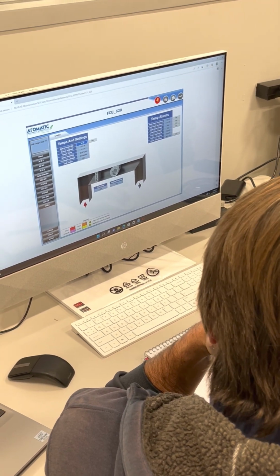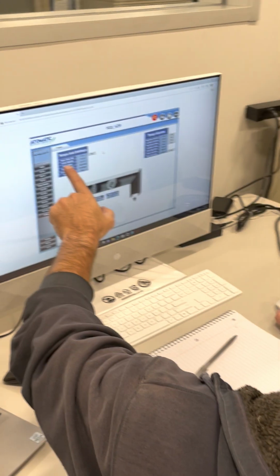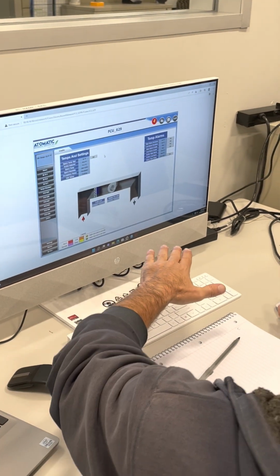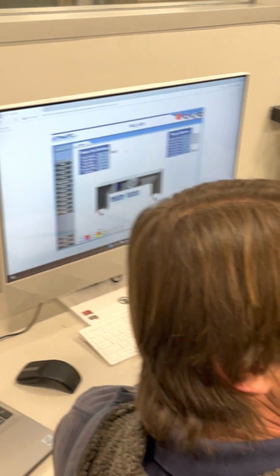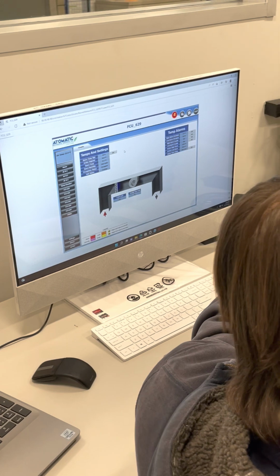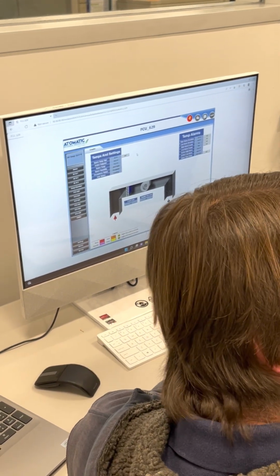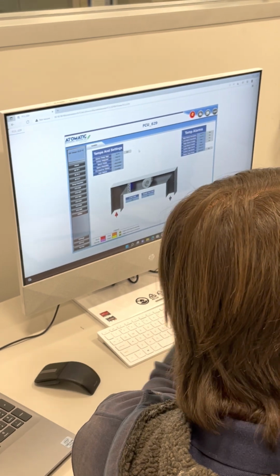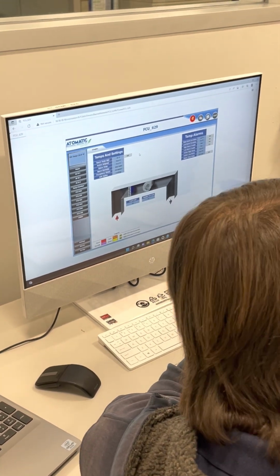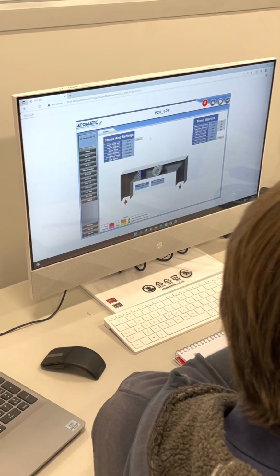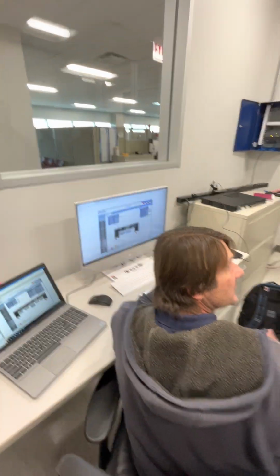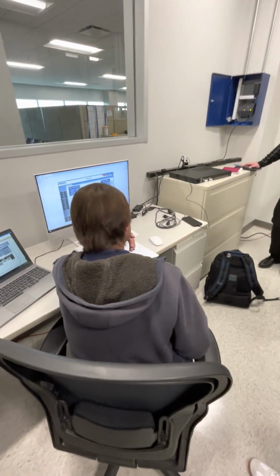You'll see that 70, and then in a minute, that active set point will drop down to 70. So what that is, it's kind of a feedback coming back. That's saying, hey, I told the guy this is what I want, and it acknowledged and said, okay, here's what my active set point is now. So if for any reason you do that and you don't see something coming back, it means something's going on, it's not getting your command.